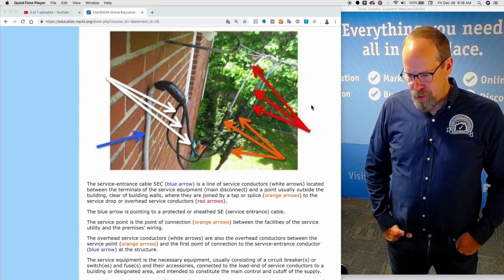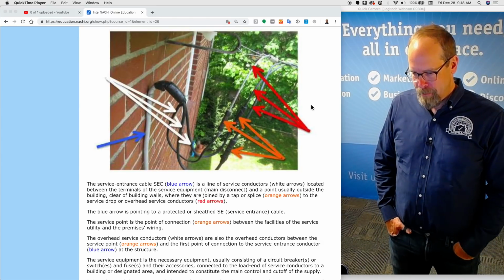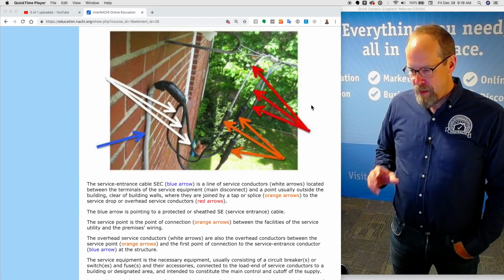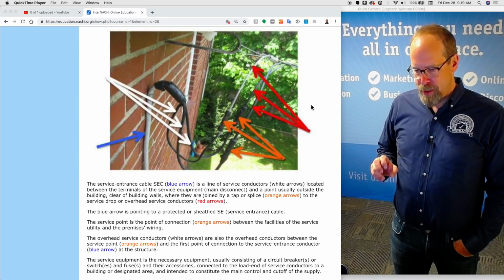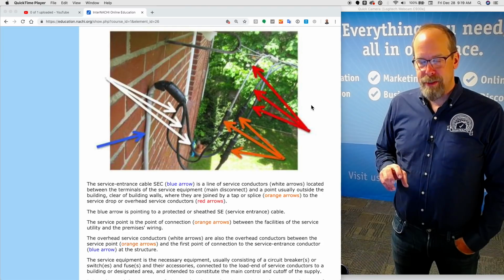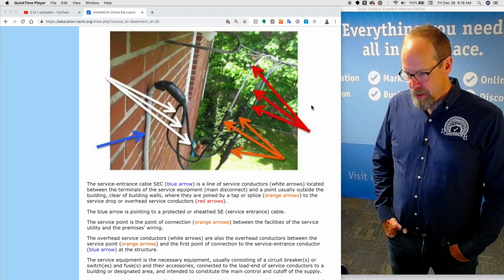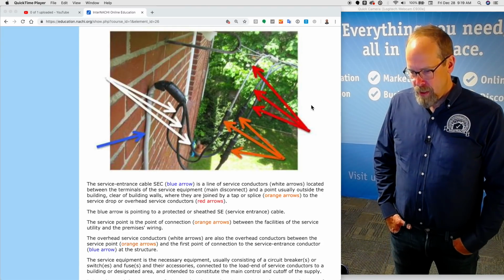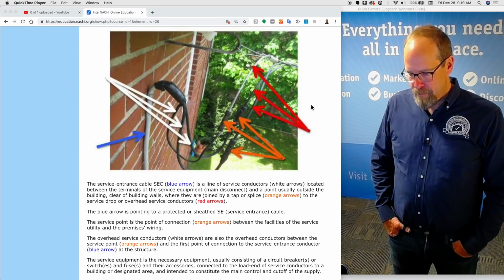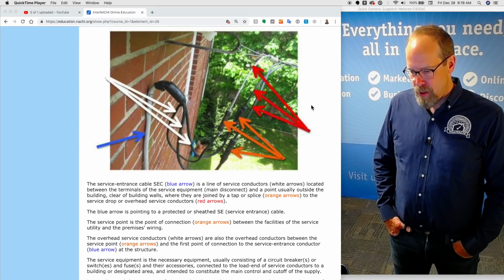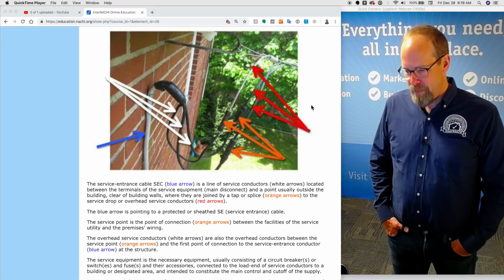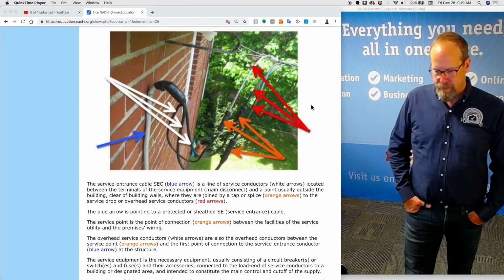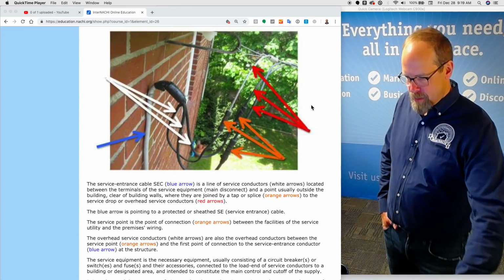The service equipment is the necessary equipment, usually consisting of breakers, circuit breakers, switches, and fuses, and their accessories, connected to the load end of service conductors to a building or designated area. And they're intended to constitute the main control and cutoff of the supply. So the service equipment is all the equipment.